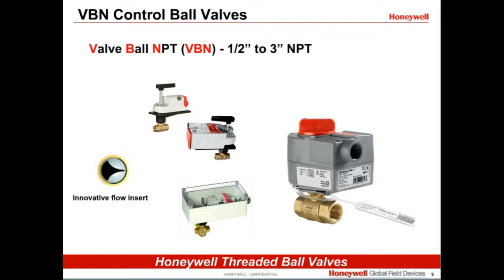These valves are called pressure-dependent valves because the amount of water that goes through them, the GPM, is dependent upon the pressure drop across the valve. Later, we will discuss a type of valve that delivers a certain GPM independent of the pressure drop. This is called a pressure-independent control valve. The part number of these valves begins with VR.